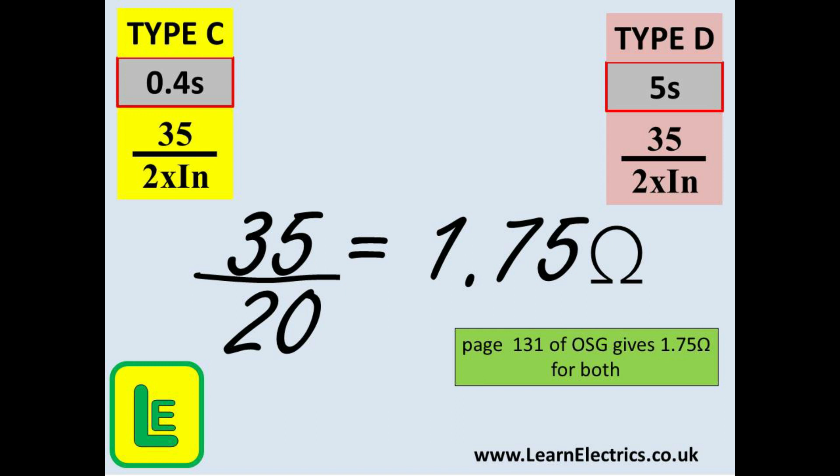Now we are going to make a slight deviation from the 0.4 second disconnections. Type D circuit breakers are often used in distribution circuits in industrial settings. Here they are protecting a feed from a distribution board to another board or a consumer unit further down the line. The disconnection time now is 5 seconds. So for a type D breaker and a 5 second disconnection time we divide 35 by twice the size of breaker. Just as we did for the type C in the last example. This gives us a calculation of 35 divided by 20 and the result is 1.75 ohms. And you can see the comparison at the top of this slide.